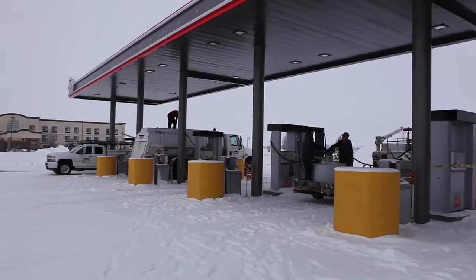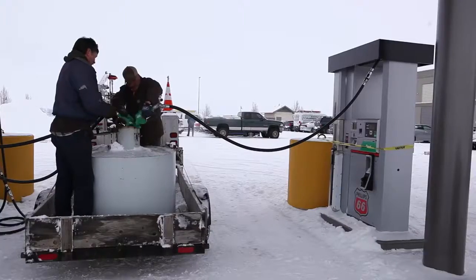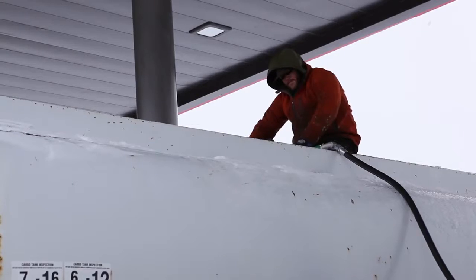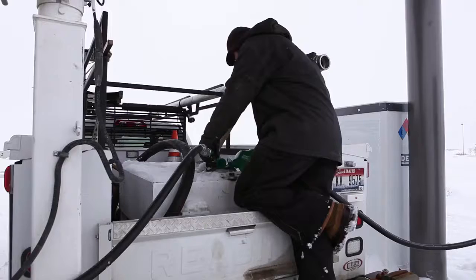We're back at the site today to check on the completed installation and test the pumps to ensure they are working correctly. Because demand on the pumps will sharply increase when the commercial nozzles are in use, we're using IQ control boxes to stage the pumps on and make sure flow remains consistent on the retail side.